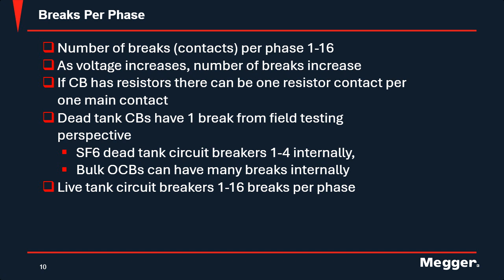If the circuit breaker does have resistors, there can be one resistor per main contact. So one break, one resistor. You can have 4 breaks and 4 resistors, 1 resistor on each break. As far as testing dead tank circuit breakers from a field perspective, it's only 1 break in the entire unit. It could have multiple breaks inside the casing, but if you remember, for a dead tank, all that linkage is inside that grounded case. So from the perspective of testing, it's 1 internal break. SF6 dead tank circuit breakers are 1 or 4 internally. Bulk oil circuit breakers can have as many breaks internally as the manufacturer sets up. And then live tank circuit breakers can generally have 1 to 16 per phase.